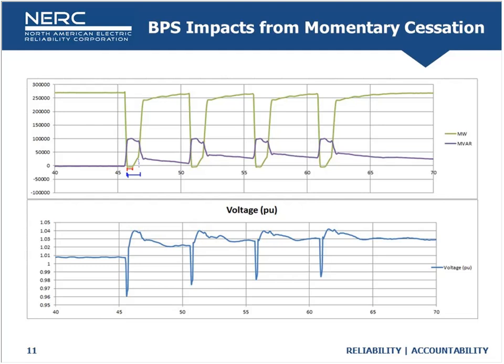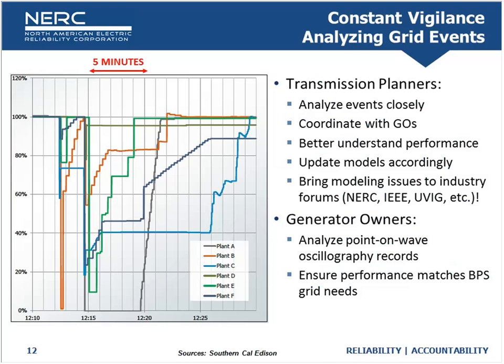These are things we're looking at and figuring out how to provide guidance on. The number one thing we're doing is maintaining constant vigilance, looking at grid events with a fine-toothed comb. The recommendations we're making are that if you're a planner, a planning coordinator, or a transmission planner, be analyzing grid events — because some of the most interesting things we've found over the last six to seven months have come from planners looking at normally cleared two-and-a-half cycle, 500 kV faults.